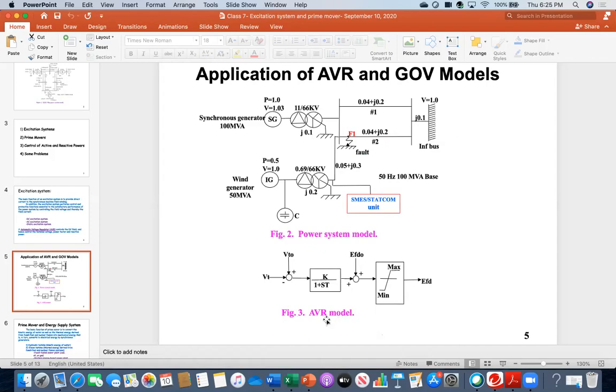So what does the AVR do? The function of the AVR is to watch or monitor the terminal of the synchronous generator. Continuously it is monitoring: is the voltage going down or going high as compared to the rated condition, the expected voltage? That's why you see the comparison. VT means terminal voltage, the measured voltage, and VT0 is the reference voltage. For example, here you want 11 kV. What is your measured voltage? Is it more than 11 kV or smaller than 11 kV? Has any fault happened, or has the voltage changed for some reason?